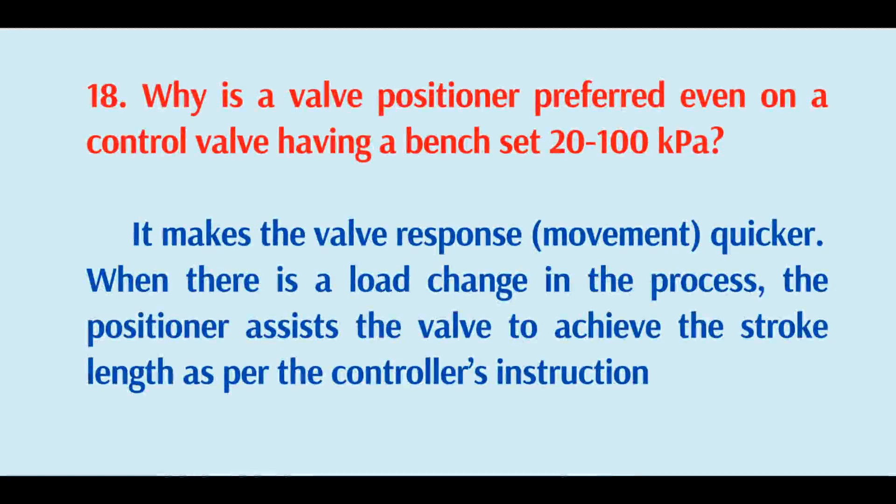Why is a valve positioner preferred even on a control valve having a bench set of 20 to 100 kPa? It makes the valve response quicker when there is a load change in the process. The positioner assists the valve to achieve the stroke length as per the controller's instruction.